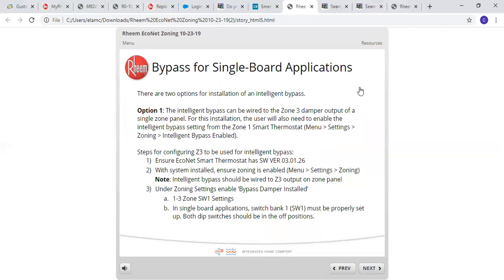Bypass for a single board application. There are 2 options for installation of the intelligent bypass. Option 1, the intelligent bypass can be wired to the zone 3 damper output of a single panel. For this installation, the user will also need to enable the intelligent bypass setting from the zone 1 smart thermostat. To get to that, you go to zoning or menu, settings, zoning, intelligent bypass enabled.